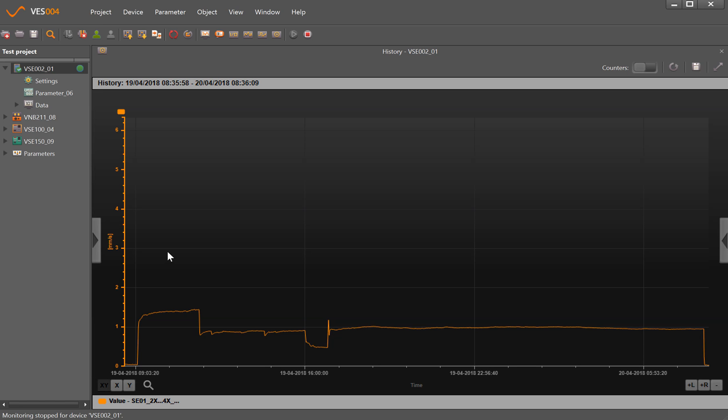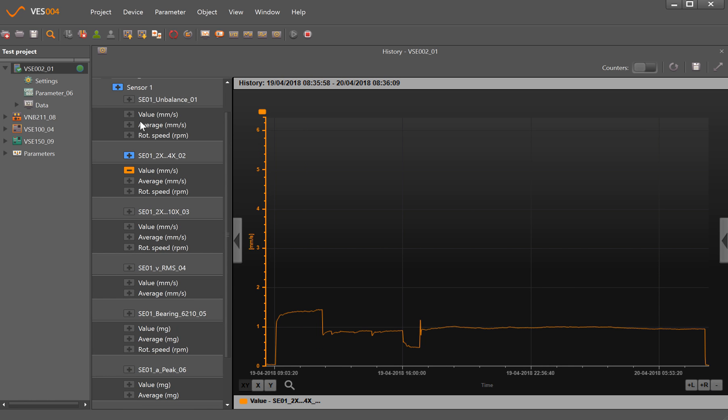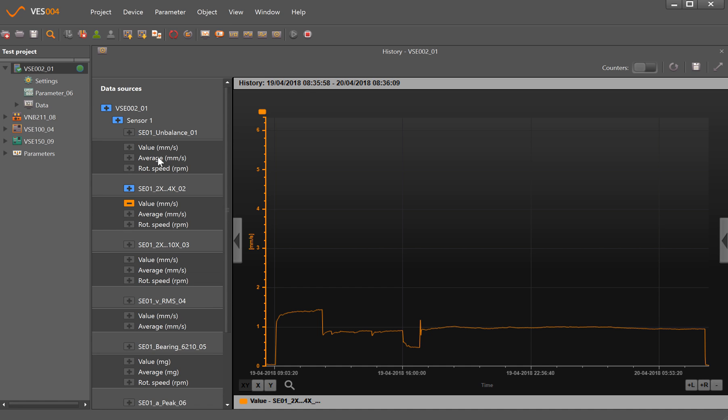As per the previous videos, you have the tabs here at the left and the right which we'll have a look at shortly, but if I click on the one on the left here this shows me all the parameters that are within this VSE from each of the sensors. What it's showing me here is whatever was the last thing that was looked at when the history was last opened. If I want to clear this, I can just go to VSE002 and the right-click mouse button has a lot of functionality, so if I just right-click and remove all from plot, that gives me a nice empty history trend to start looking at some data.